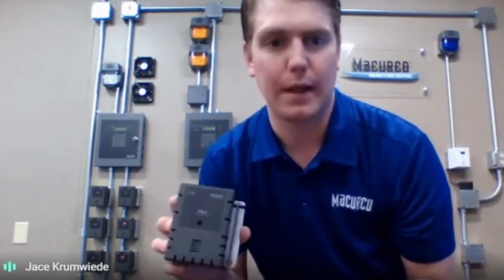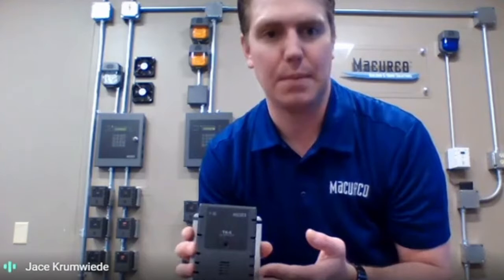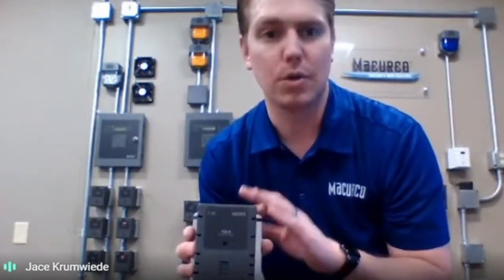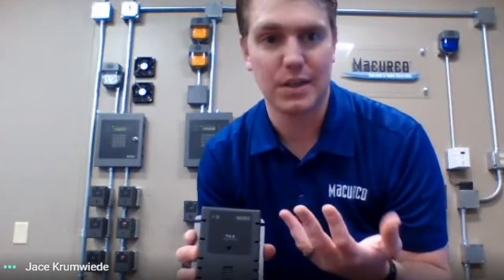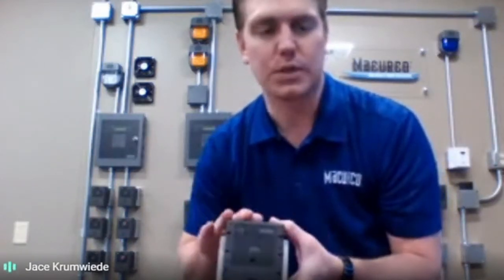Now we'll transition over into the Macurco building and home products. So these can be used standalone, as Brent mentioned. Here's a single unit. I have a bunch more on the wall, but this is a 6 series, part of our commercial series detectors. Wide variety of gas types, carbon monoxide, nitrogen dioxide, combustible gases, also work with a lot of different toxics like hydrogen sulfide, ammonia, you'll get into oxygen, carbon dioxide. This product line is growing very significantly, so a lot more gases to come, but general purpose type unit, 4-inch by 4-inch electrical box. They do have onboard relays, so you can do localized control of exhaust fans, turn on a strobe to a fire panel. You can do all sorts of stuff with this.